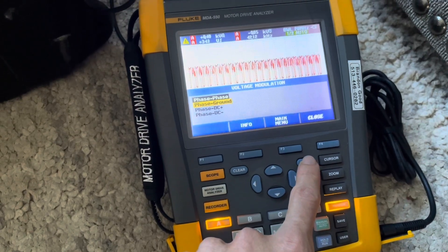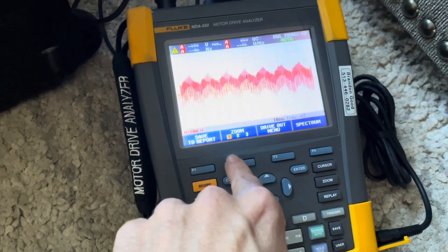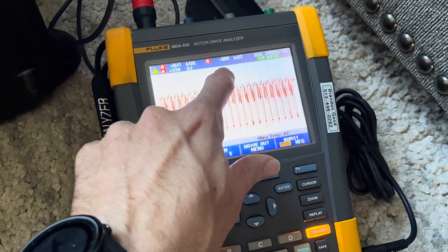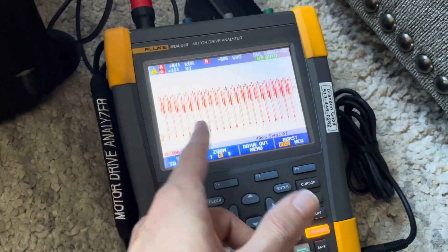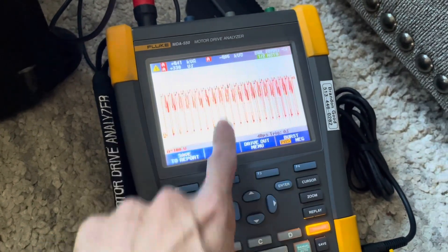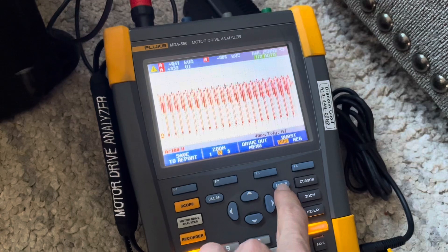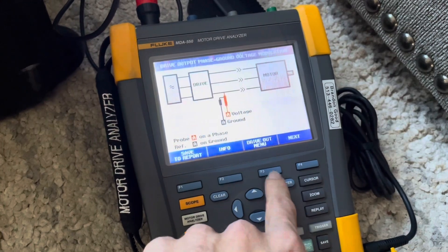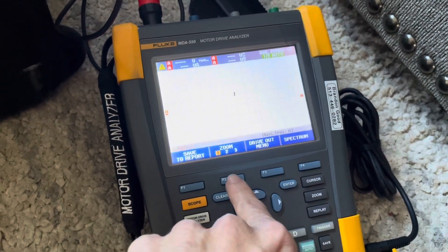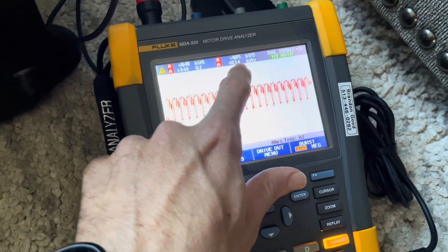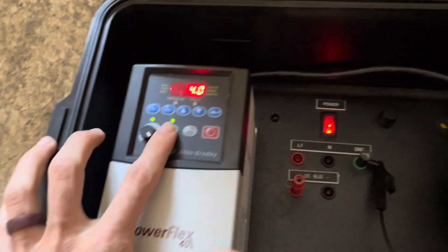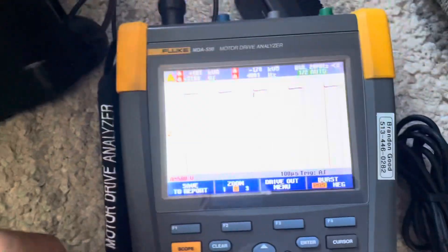You need to be in phase-to-ground, not phase-to-phase. If you select phase-to-phase and go to Zoom 2, you can see there's no frequency reading — and that's the reading we want. So go back, select 'Voltage Modulation,' choose phase-to-ground, then hit Zoom 2 and you can see kilohertz. That's where we're going to see the carrier frequency.